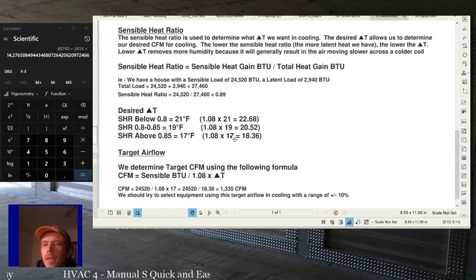All right? So there's some math involved, but it's not that bad. If you just keep it simple in your head and follow the steps, it's pretty easy. As long as you have the sensible load of the house and the latent load of the house, you should know how many CFM you need in the house after you run a couple numbers. All right? It's easy as that. It doesn't matter how big the house is or how many windows you have or whatever. You've already got the load calc. It tells you what the sensible load is, tells you what the latent load is. We know what our target CFM should be.